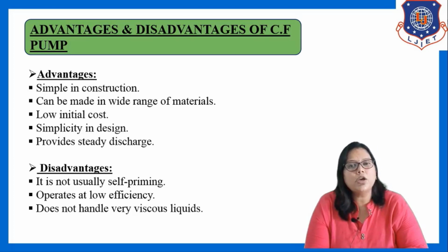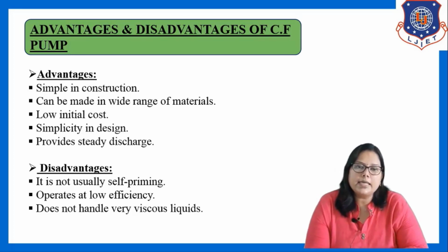The efficiency of the centrifugal pump is low as compared to other pumps. And the last disadvantage of using a centrifugal pump is that it does not handle very viscous liquid. When we are transferring a liquid which is viscous in nature, at that time we cannot go for a centrifugal pump. So these are the advantages and disadvantages of using a centrifugal pump.